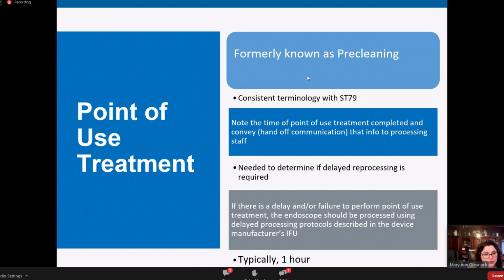That is in the instructions for reprocessing of the endoscope from your major scope manufacturers. And it's not optional. If that scope sat for longer than 1 hour, then you have to follow that process as outlined in the manual. The problem with that is a long-term submersion in the detergent solution prior to even starting manual cleaning. And you do have to look at your type of scope and the manufacturer to know what exactly the guidance is. But generally, it's soaking for up to 10 hours for your GI scopes and up to 1 hour for your surgical or small diameter flexible scopes. That's a long time, and you're going to tie up your sink. So we want to avoid this as much as possible, that longer than an hour delay.